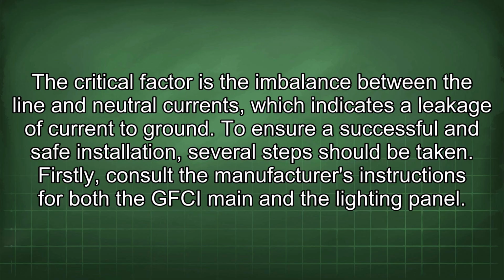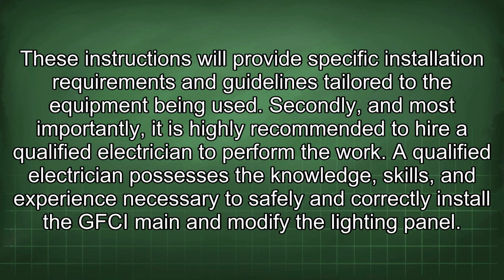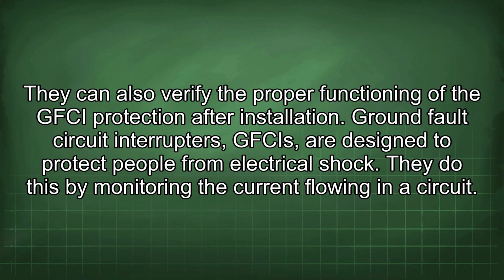To ensure successful and safe installation, several steps should be taken. Firstly, consult the manufacturer's instructions for both the GFCI main and the lighting panel. These instructions will provide specific installation requirements and guidelines tailored to the equipment being used. Secondly, and most importantly, it is highly recommended to hire a qualified electrician to perform the work. A qualified electrician possesses the knowledge, skills, and experience necessary to safely and correctly install the GFCI main and modify the lighting panel. They can also verify the proper functioning of the GFCI protection after installation.